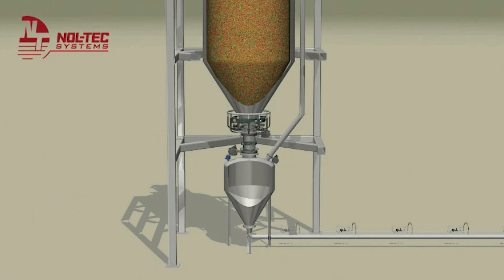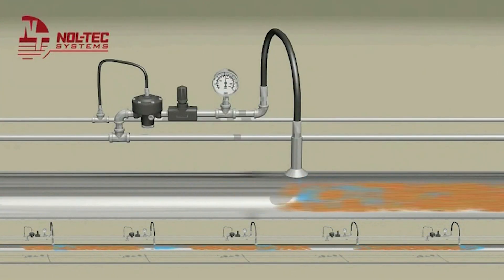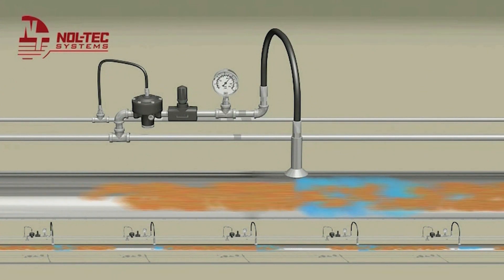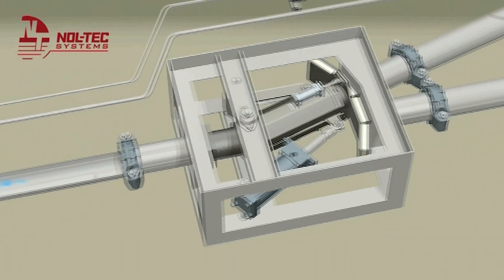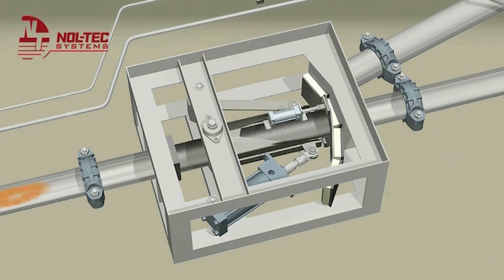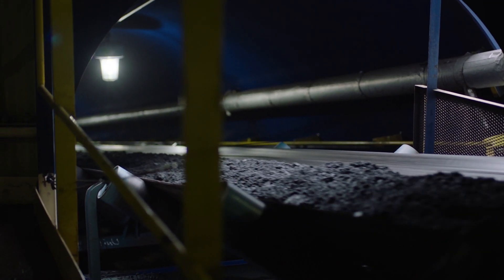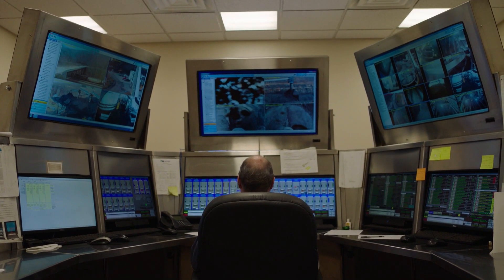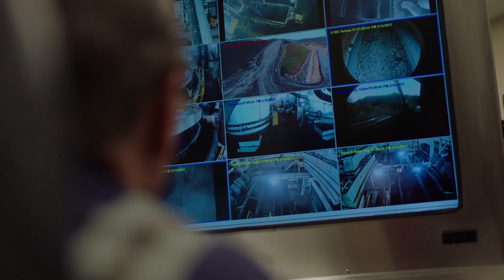This short animation shows how dense phase conveying works. The Ramsorb material is loaded into a transfer vessel at the bottom of the silo. The vessel is pressurized and product delivery begins. Noltec's air assist technology introduces a small amount of air along the entire convey line, moving the material slowly through the process, limiting wear on convey line components and increasing reliability. Hose switches can be used to alter the conveying path if needed. At the application point, dust collection separates air from the material. The material is metered onto the coal belt using loss-in-weight technology, and the application rate is managed using near-infrared moisture sensing technology by the plant operations staff in the control room.